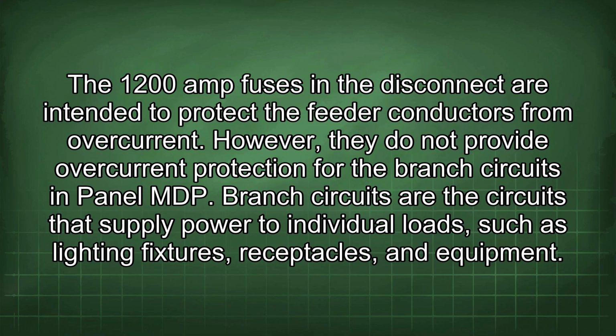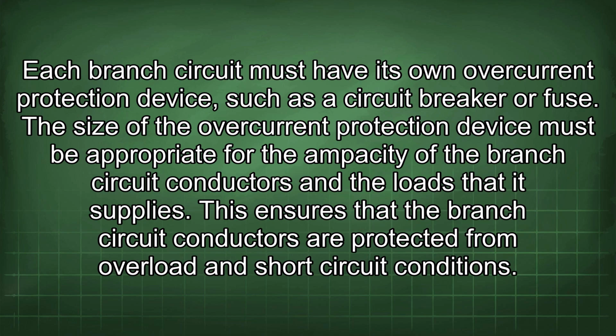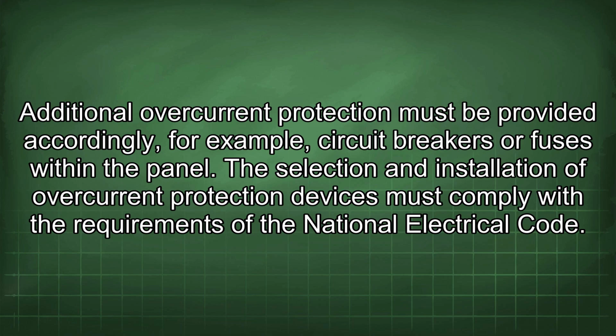The 1200 amp fuses in the disconnect are intended to protect the feeder conductors from overcurrent. However, they do not provide overcurrent protection for the branch circuits in panel MDP. Branch circuits are the circuits that supply power to individual loads such as lighting fixtures, receptacles, and equipment. Each branch circuit must have its own overcurrent protection device, such as a circuit breaker or fuse. The size of the overcurrent protection device must be appropriate for the ampacity of the branch circuit conductors and the loads that it supplies. This ensures that the branch circuit conductors are protected from overload and short circuit conditions. Additional overcurrent protection must be provided accordingly, for example, circuit breakers or fuses within the panel.